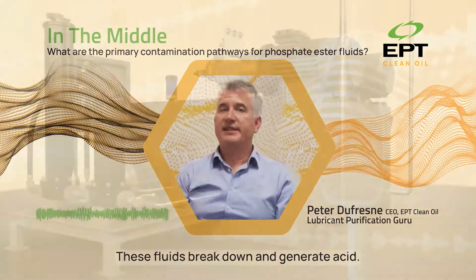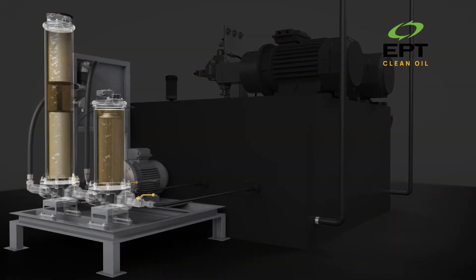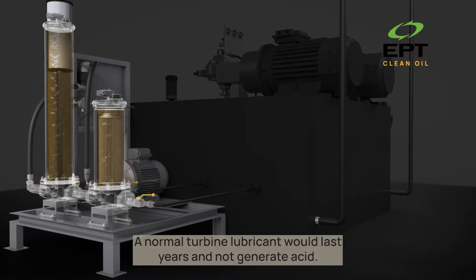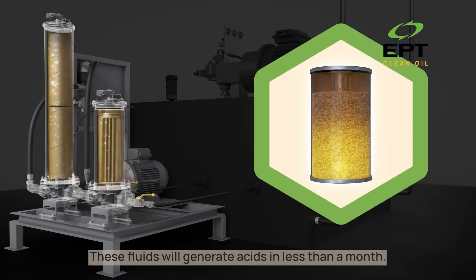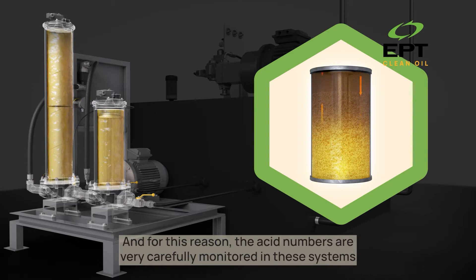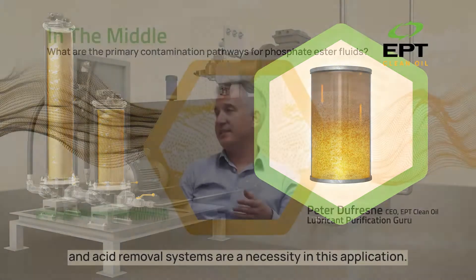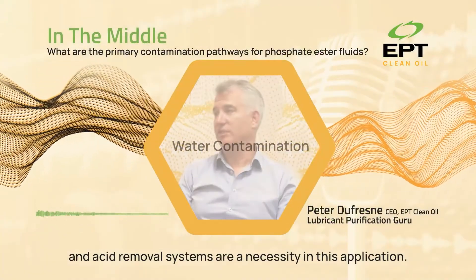These fluids break down and generate acid. A normal turbine lubricant would last years and not generate acid. These fluids will generate acids in less than a month. They are generating sufficient quantities of acid, and for this reason, the acid number is very carefully monitored in these systems, and acid removal systems are a necessity in this application.